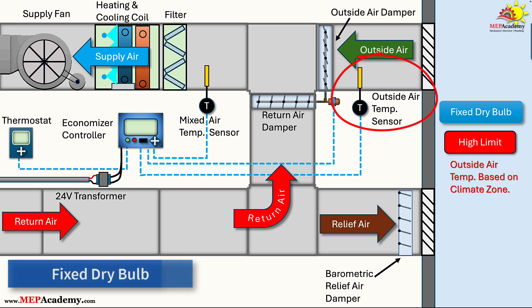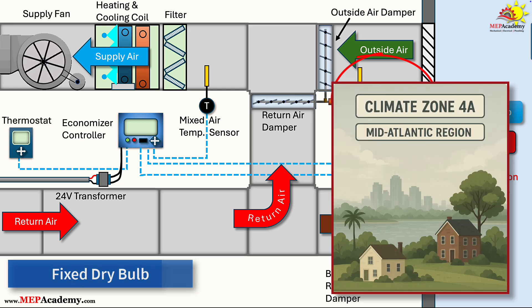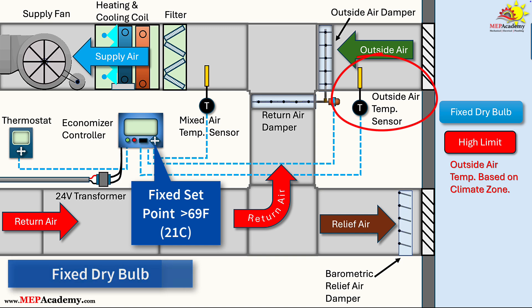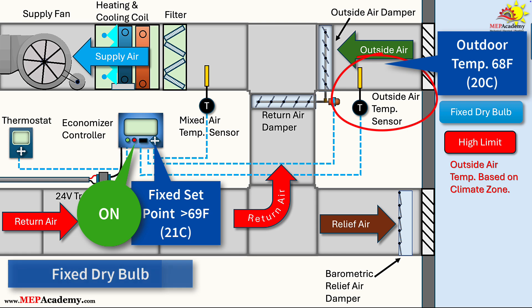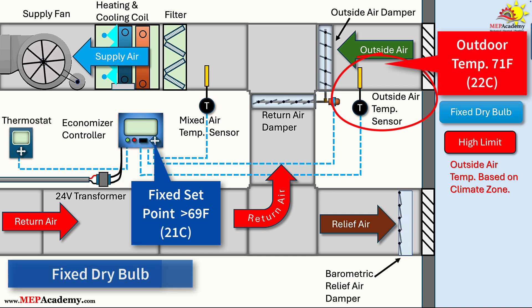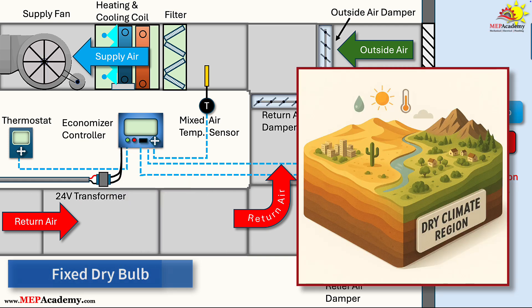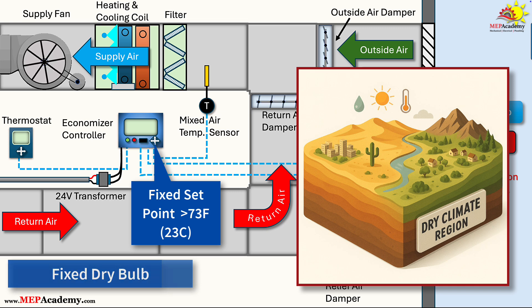Consider a commercial building in a moderate climate, such as Climate Zone 4A, such as parts of the U.S. Mid-Atlantic region. The fixed dry bulb set point might be set at 69°F (21°C). On a day when the outdoor temperature is 68°F, the economizer enables, allowing outdoor air to mix with return air to cool the space. However, if the temperature rises to 71°F (22°C), the economizer shuts off to prevent warmer air from entering, shifting the load to the mechanical cooling system. If you're in a drier area, like Zones 1B through 5B, the fixed dry bulb might be set at 73°F (23°C).